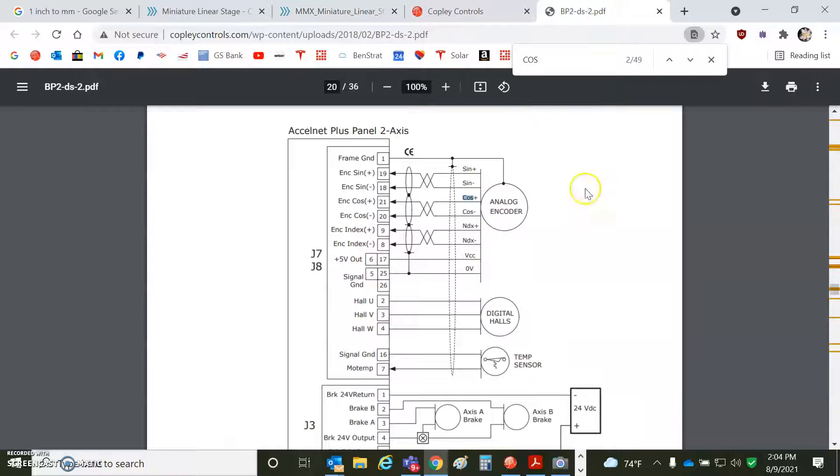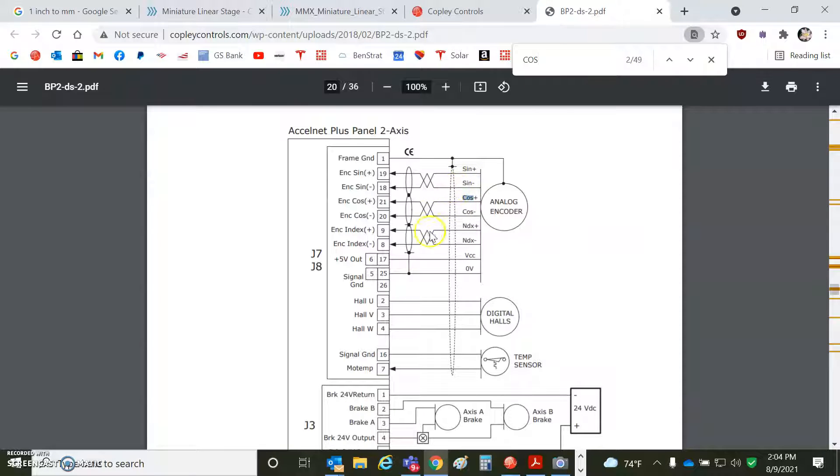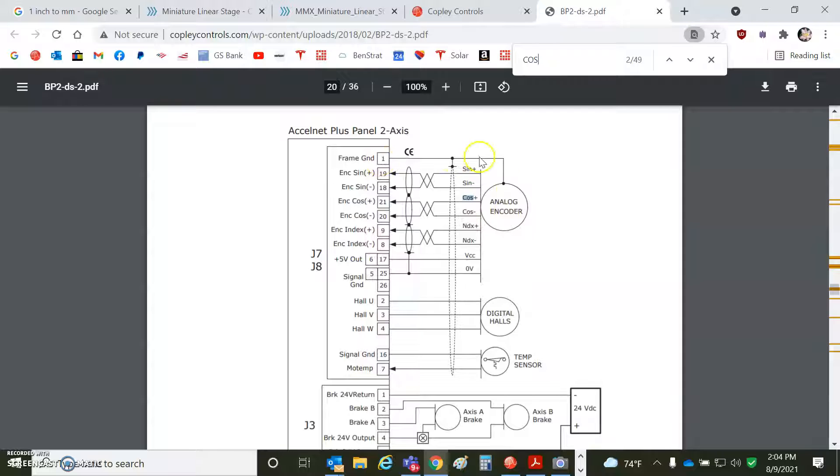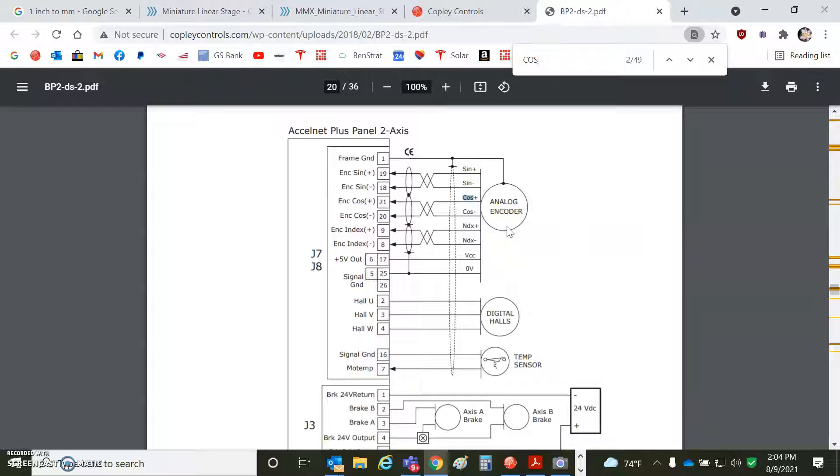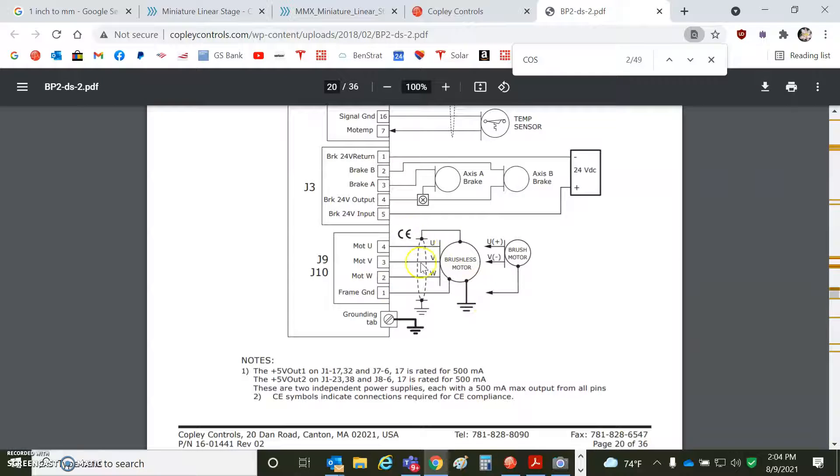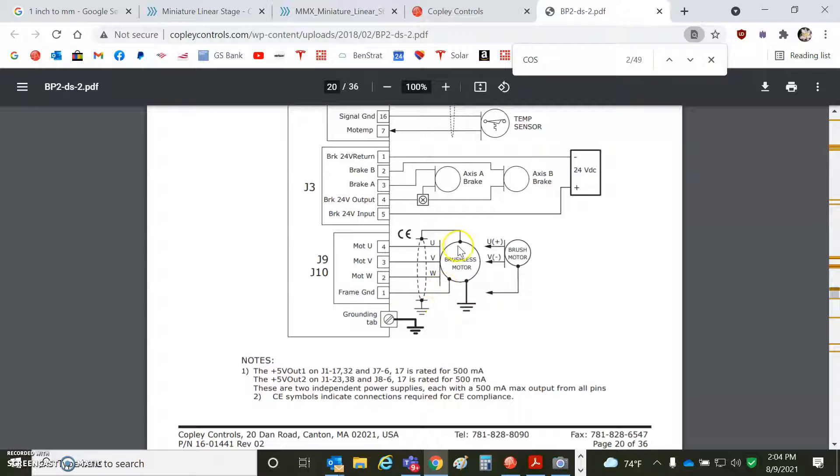And so to look at the BP-2, of course, there's a sine cosine, two wires twisted, shielded. If there's an index, we can hook it up. Or if there's limit switches, I'll show you that in a minute. But we show the shield connected to pin one. The shield is not connected to the motor case. And then down here, we show the motor case connected to Earth and the shield connected to Earth. You can hook up the shield to the motor case. That's fine. But the shield, it shouldn't be the only path to Earth.